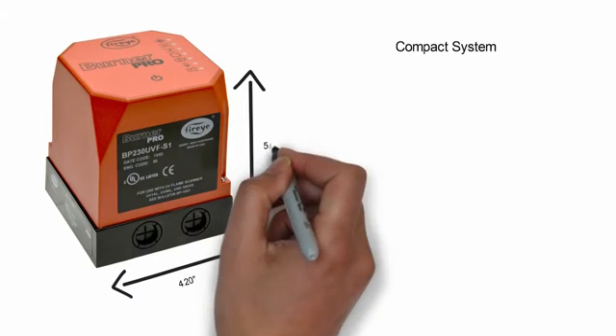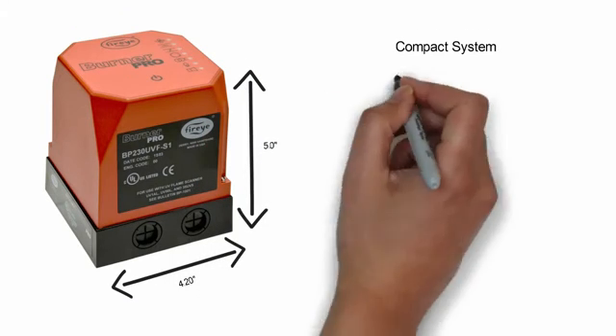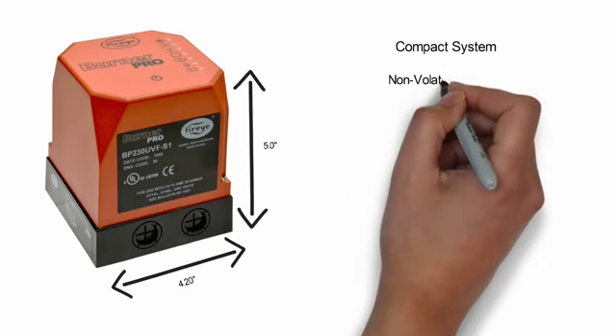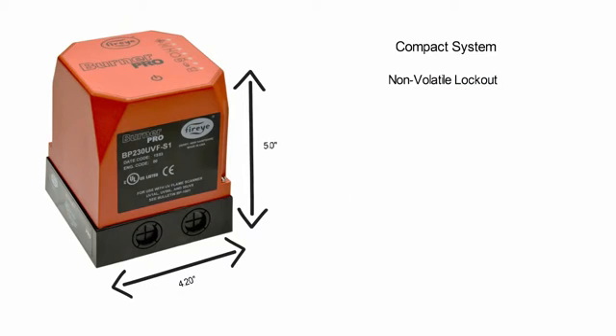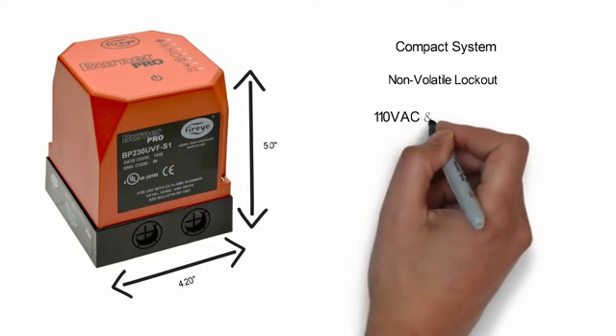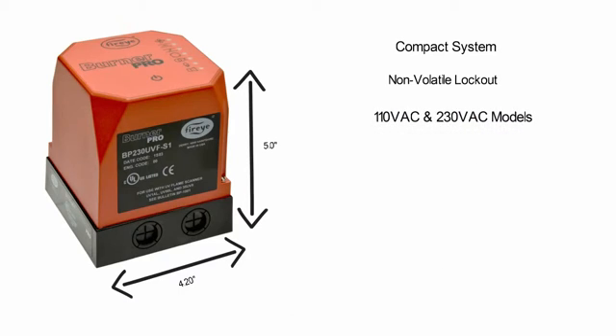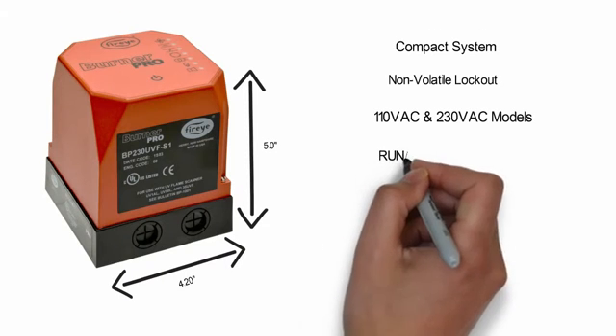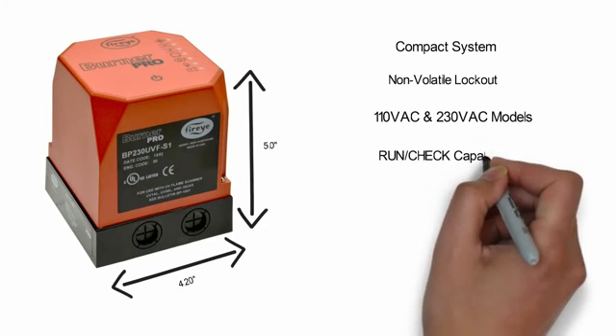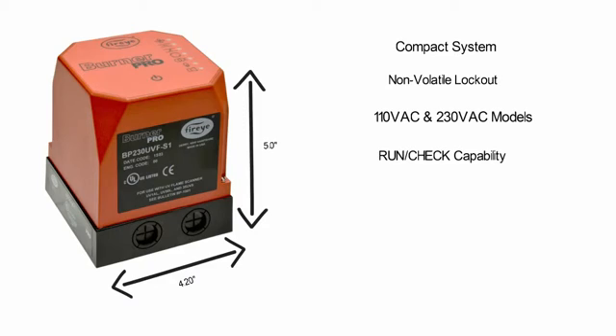Pre-programmed operational timings ensure safe operation of the burner system. Non-volatile lockout capability is used to store lockout information even in the event of a power outage. 110VAC and 230VAC models available for greater flexibility in your application. Run check capability allows the system operator to stop the program sequence in the purge, ignition, PTFI and MTFI positions during system commissioning.